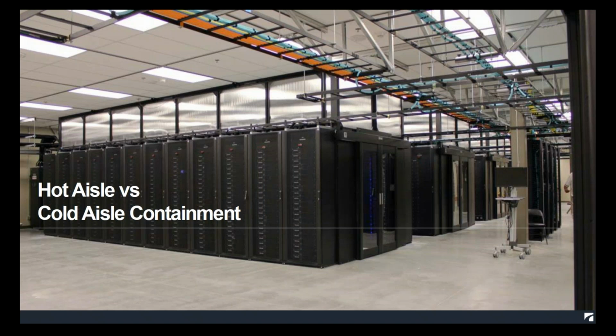We do hot aisle containment in all of our new data centers. And what that allows us is, in addition to the efficiency, a great deal of flexibility. So if you contain your cold aisle, you're designing that cold aisle typically for a certain amount of airflow, and you're not going to get more than that amount of airflow. So that pod of cabinets, you have a certain amount of airflow that you can support.